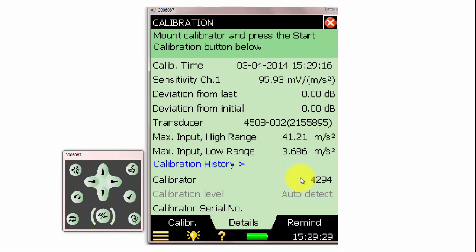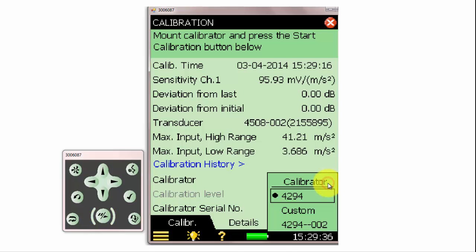The default calibrator type for accelerometers is the type 4294. If we're using a different calibrator, such as the 4294-002, which can be used with heavier accelerometers, we can select that, or a custom calibrator type.